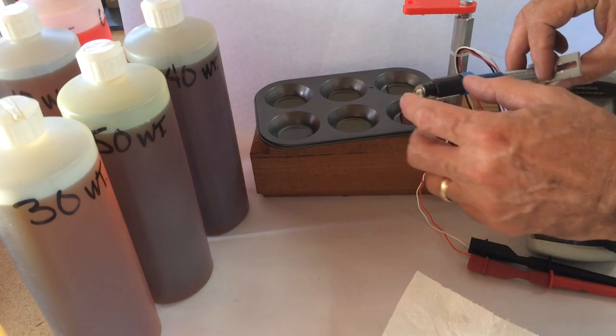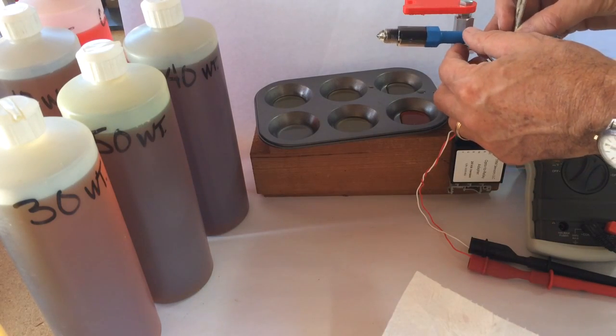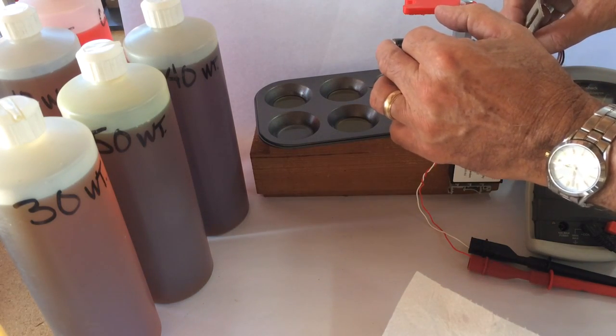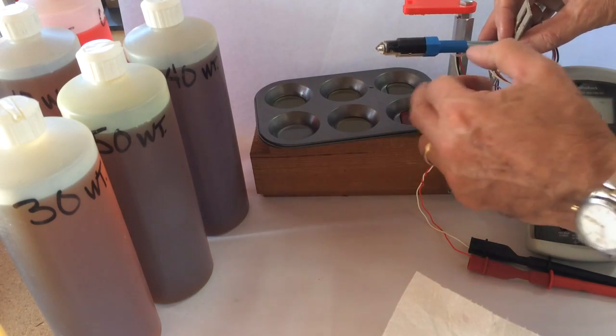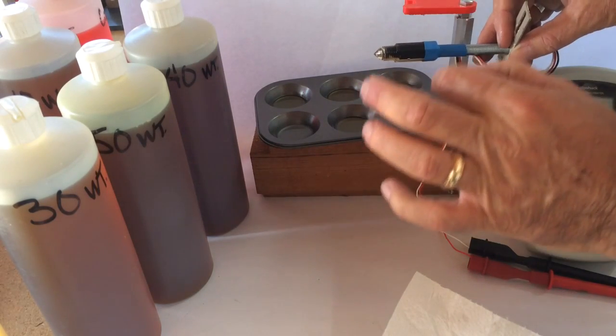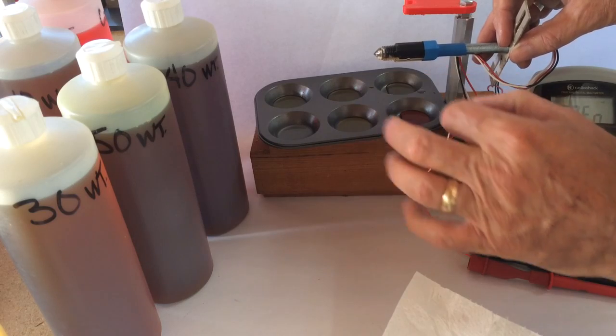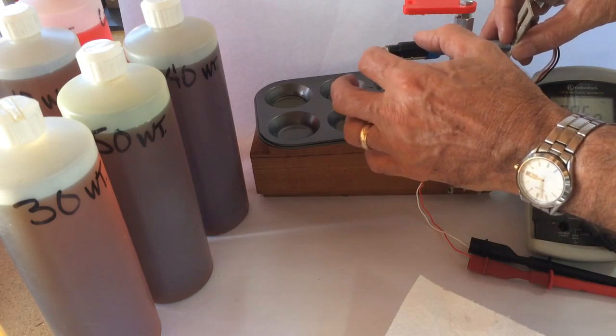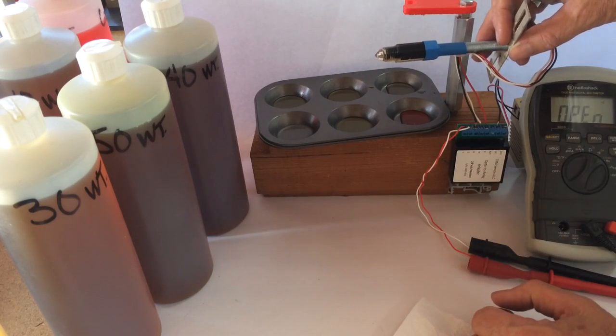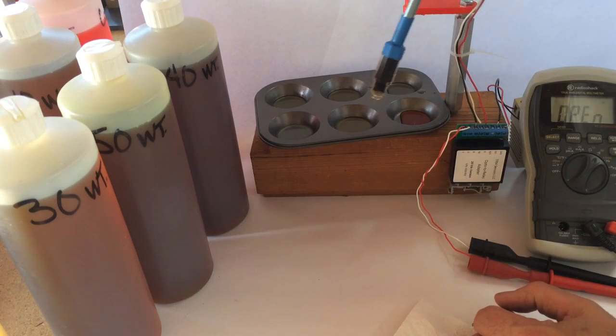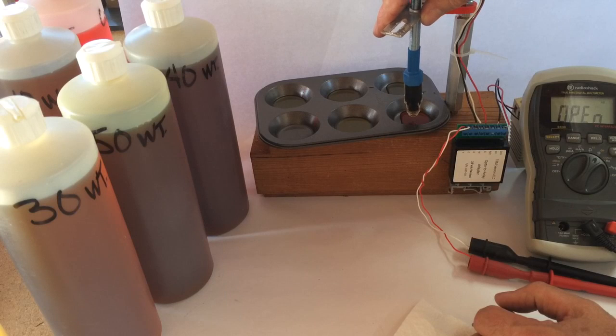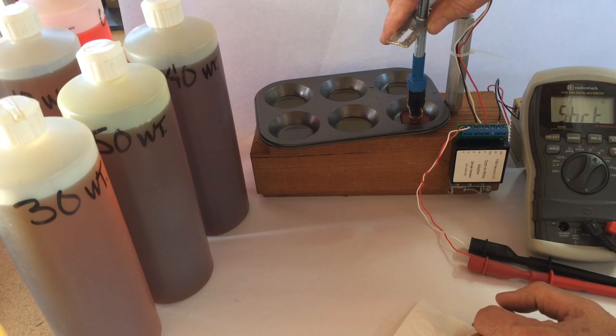Again, you can see the nose cone, it tapers to a point, and we're just basically almost resting on the surface of the tin as if you had lowered the probe in until you felt some resistance and just straightened out the slack in the cable.